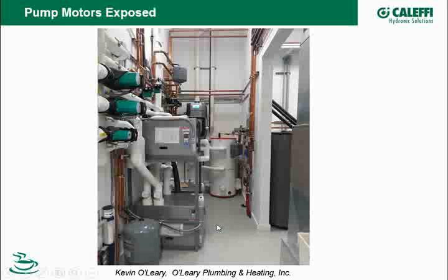You can see one of our Thermocom tanks in the background, and he's got that insulated right tight up to the tank. Then you can see the fittings that he didn't use down here, where he's put nipples and caps on them. He's also put some insulation on that, because again, with these chillers, you don't want all this pipe sweating and dripping in the mechanical room here. So I thought that was some nice details and a nice piping job, insulation job also.